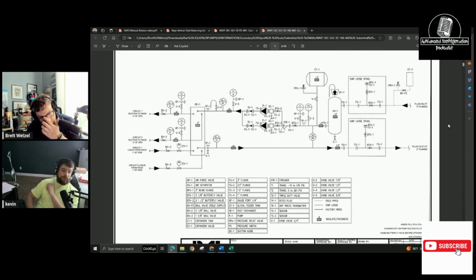The geo loop is the condenser in the summertime, and in the wintertime, it's an evaporator. So they're taking water from the ground, it's a ground source heat pump, and mixing it in this chilled water buffer tank. Okay, so the glycol for the geo and the chilled water are the same loop. In a sense. They're taking the geo water from the wells and dumping it in the chilled water buffer tank. Then the chilled water gets chilled by the rack, which makes load for it to heat in the wintertime. It is a giant water source heat pump that also does the refrigeration.